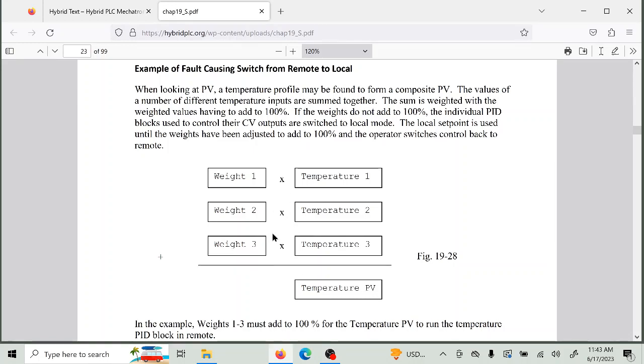So they could jockey around with these, and in manual mode, the valve stayed in its last position. In other words, everything just stayed as is until they got the thing corrected. But they'd sound the alarm, somebody would come in and fix it, and then they would make sure these numbers added to 100%. It's interesting to note that different people, different shifts ran these with different numbers. And I thought that was kind of interesting because somebody ought to come in and say, well, this is the right way to run it, and that was it.